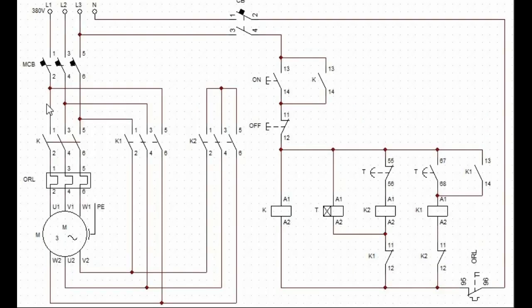First, let's see how the power circuit wiring is done before we move to the control circuit. Three phases L1, L2, and L3 enter the MCB input, and from the output of the MCB power is supplied to the input of contactor K.